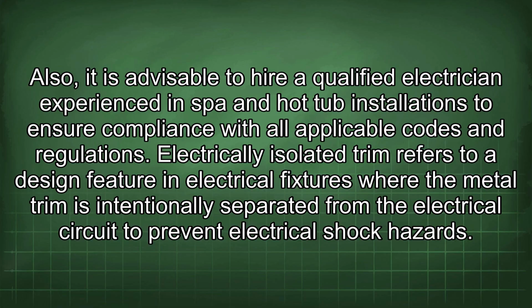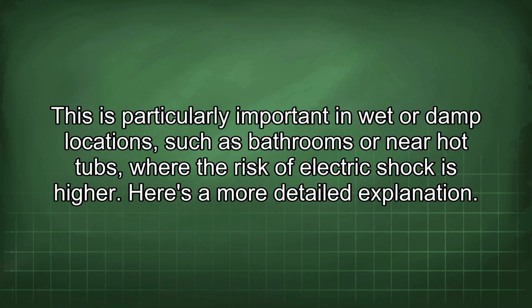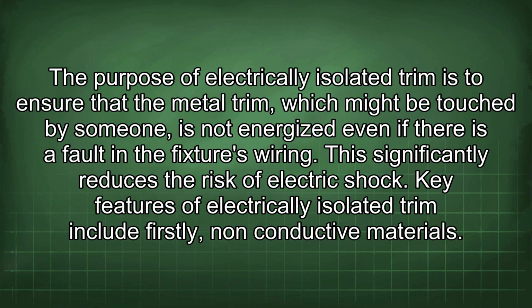Electrically isolated trim refers to a design feature in electrical fixtures where the metal trim is intentionally separated from the electrical circuit to prevent electrical shock hazards. This is particularly important in wet or damp locations, such as bathrooms or near hot tubs, where the risk of electric shock is higher. Here's a more detailed explanation. The purpose of electrically isolated trim is to ensure that the metal trim, which might be touched by someone, is not energized even if there is a fault in the fixture's wiring. This significantly reduces the risk of electric shock.